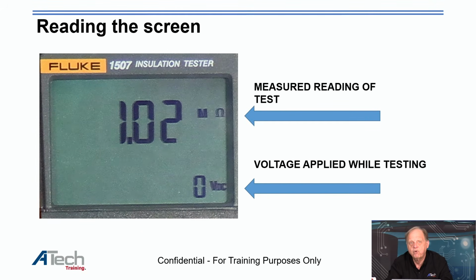Now this meter is a little different, it'll be a bit different live, which we'll do in just a few minutes. First we're going to measure the reading, and it says 1.02 megohms, that's a big M. It would also tell you how much voltage is being applied while testing the circuit, so we're looking for 500 volts to go across this circuit when we're doing it. So let's look at the readings we've got here.